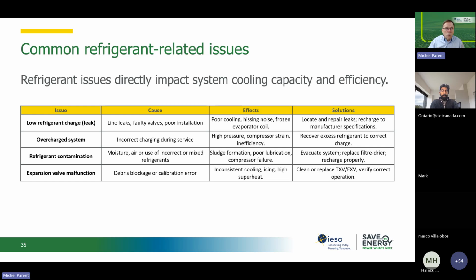The most common issues with refrigeration systems, and when I say refrigeration, I mean air conditioning, by the way, I don't mean refrigeration as we see in a cold room. So: low refrigerant charge and high refrigerant charge. The overcharged system is the least common of the two. The low refrigerant charge is by far the most common. Usually you'll see that, especially on DX systems, and most operators will know that, by a frozen evaporator coil. That is the dead giveaway.